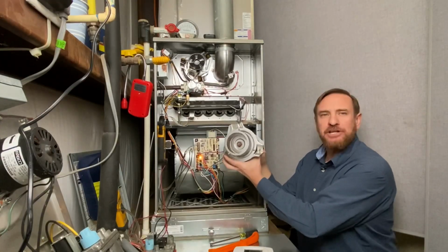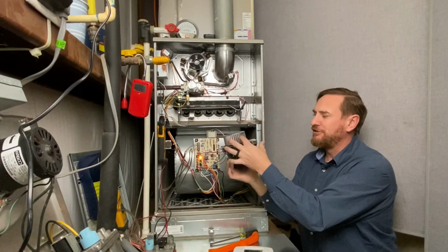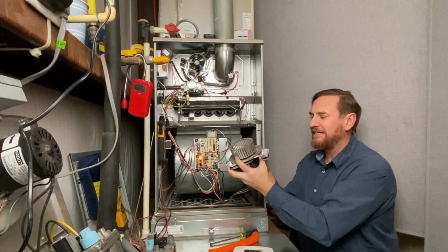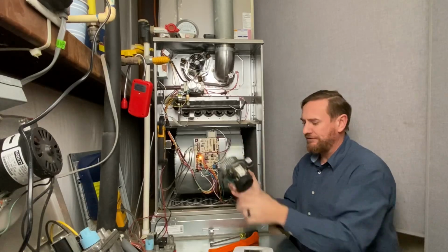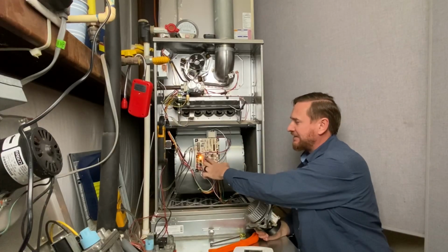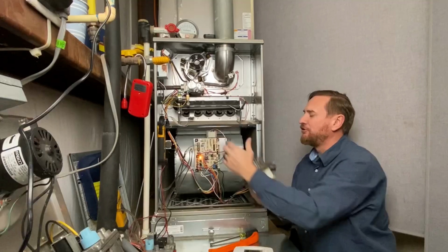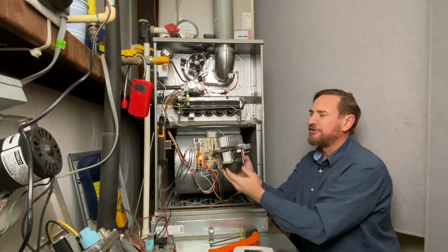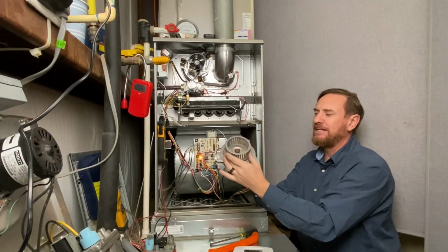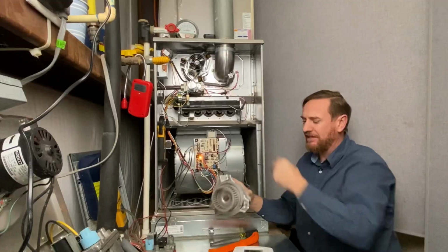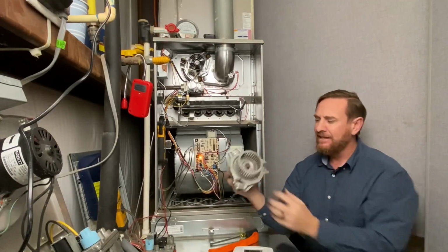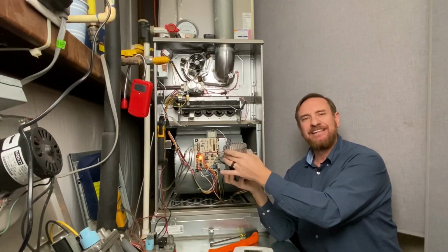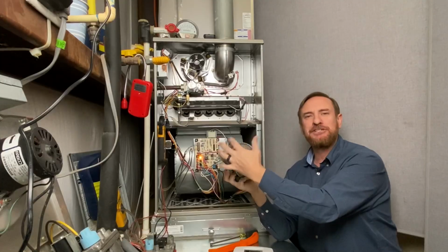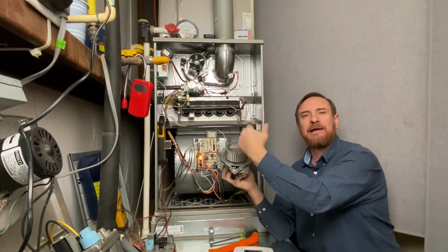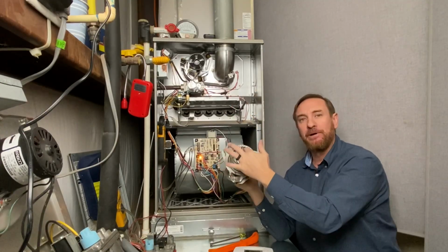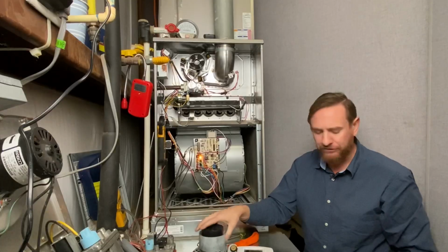It's just like a miniature blower motor. So you've got these little fins right here, and these usually come in a complete kit. So when this gets 120 volts, on this IFC, it's got these relays that energize 120 volts to this motor. This motor starts running, and as this motor is running, it starts pulling that draft and forcing it through that vent pipe. These fins can easily get corroded, burned up, especially if you have a leaking flue pipe or incomplete combustion. These things will burn completely up. So it's very important that those are working.